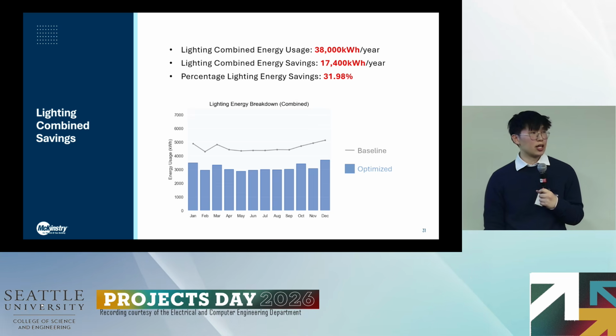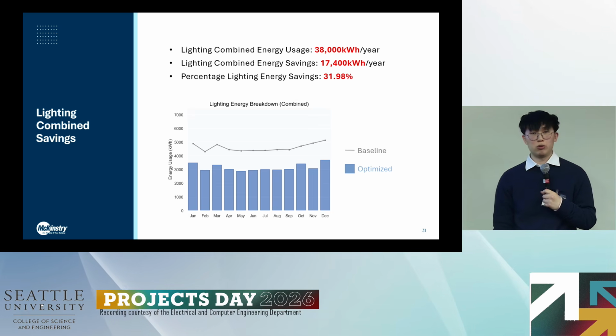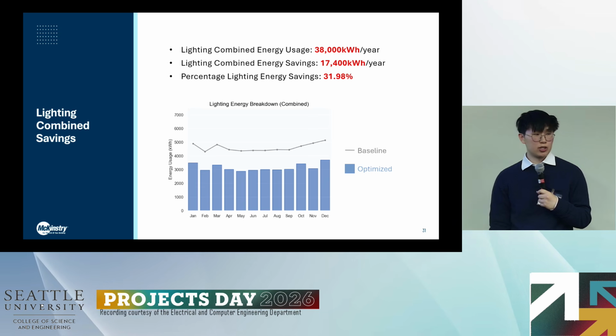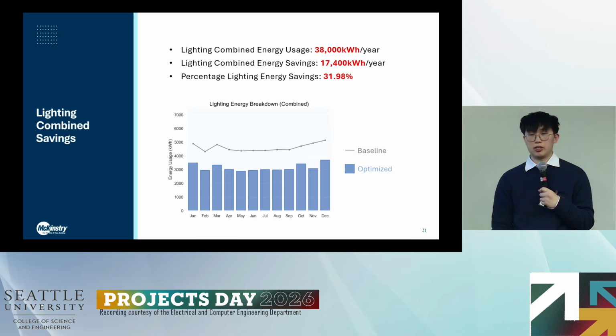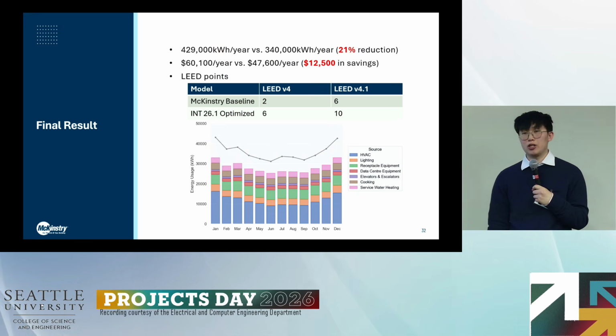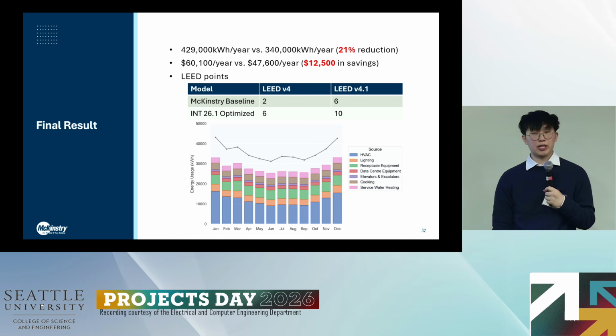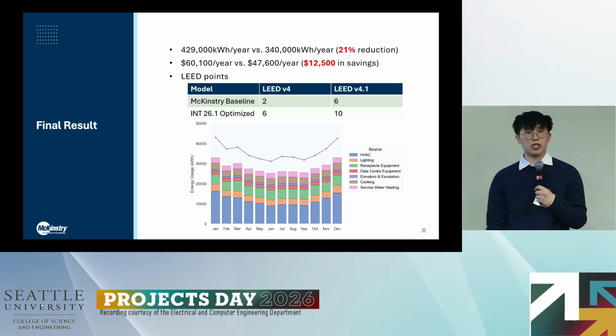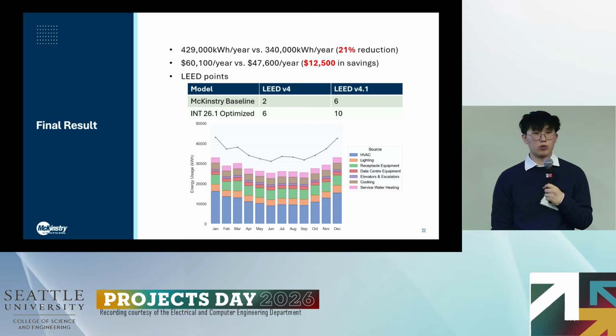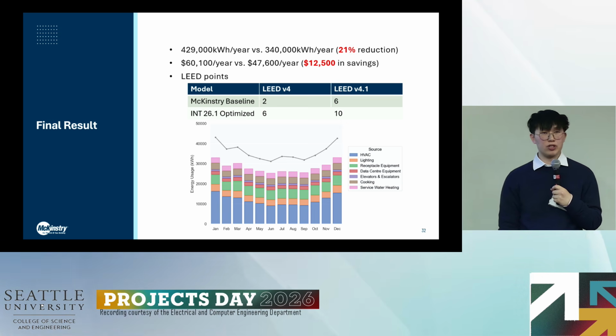Combining all of the aforementioned lighting strategies, we see that SUMO will use 38,000 kilowatt hours, and this equates to about 17,400 kilowatt hour reduction from the baseline, or a 32% reduction. And combining all of the HVAC strategies and the lighting strategies, we see a 21% reduction from the baseline, and we'll save about $12,500 per year. Going on to LEED points, the McKinstry baseline that we were given gained 2 points under LEED v4 and 6 points under LEED v4.1. Our model gained 6 points under LEED v4 and 10 points under LEED v4.1.